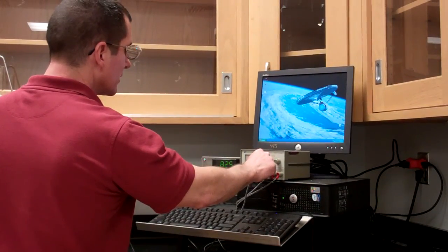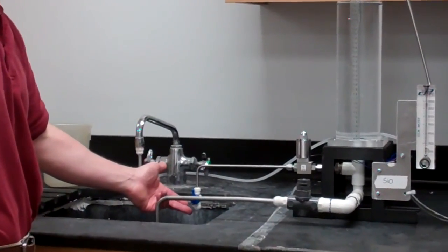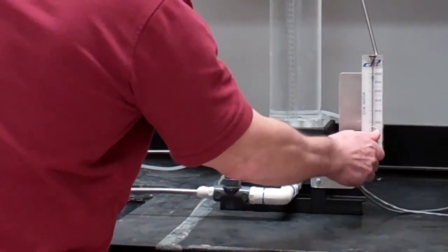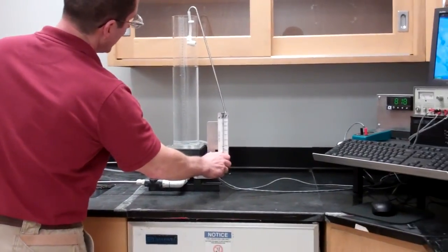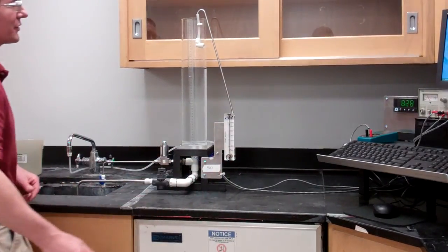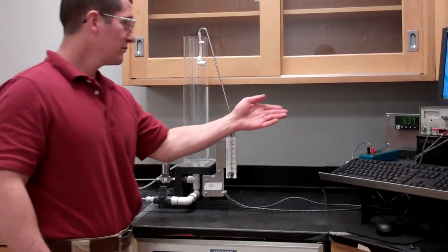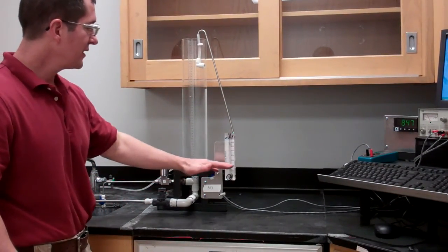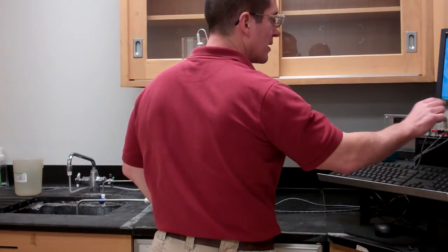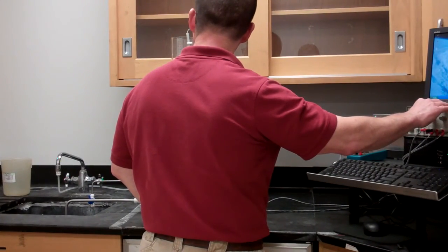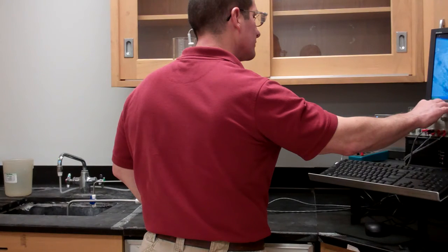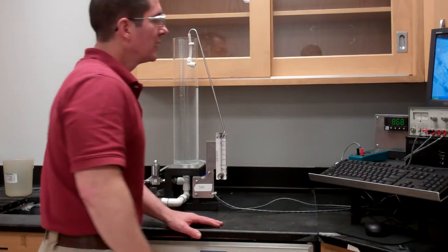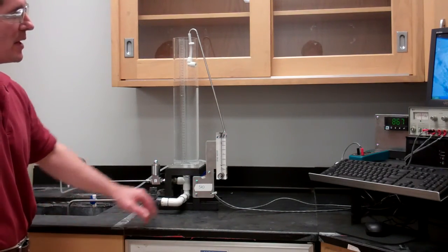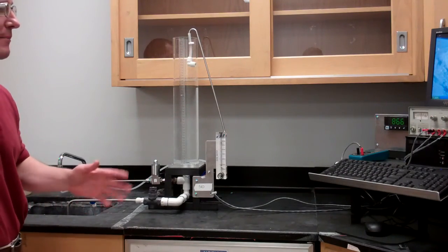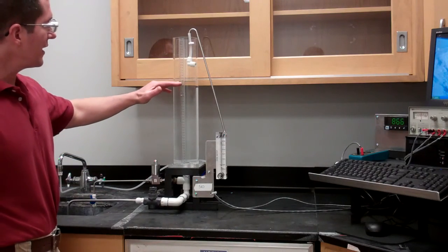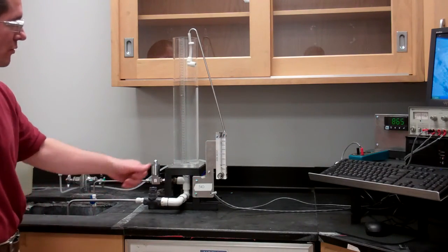As I apply a signal, my valve starts to open up and some fluid drains out. Of course, the idea with level control is you're going to have some flow going into the tank and some flow going out, which you have to balance in order to keep the level constant. Now, you can already see that the level's rising, which means that the inflow is greater than the outflow. So that means I need to send more power to my final control element. I'm pretty close now to having it balanced, it looks like. Maybe dropping a little bit. As that signal goes down, that means the outflow from the valve is greater than the inflow going into the tank, which you read on the rotameter here.